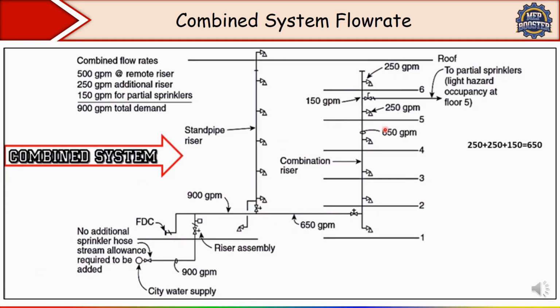Now let's say you have a partial sprinkler, if you see in this image, you will understand. As I told you, partial sprinkler protection means that only certain areas of the building are covered by sprinklers. In this image, only on this floor we have a sprinkler, rather than having a full sprinkler system throughout the entire building, okay.